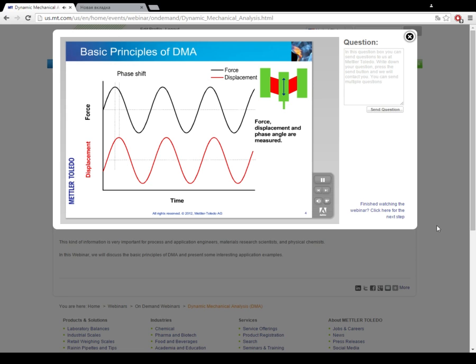Now let me explain the shear measurement mode. The sample holder is shown schematically in the red and green diagram in the upper right-hand corner of the slide. In this mode, 2 identical test specimens are held between 3 discs that are clamped together to form a sample holder. The middle disc is moved up and down under instrument control.